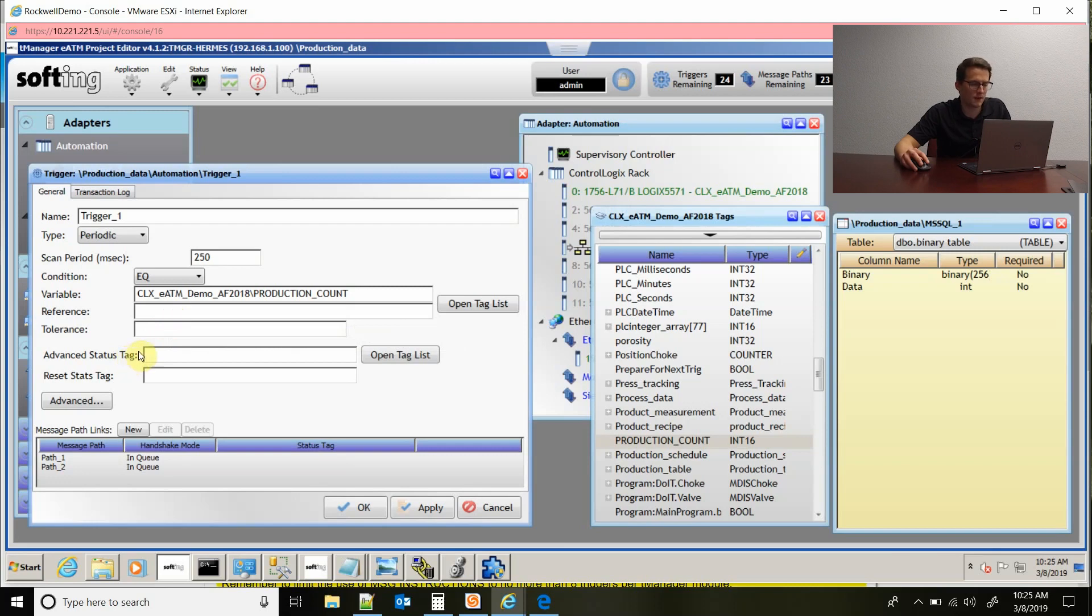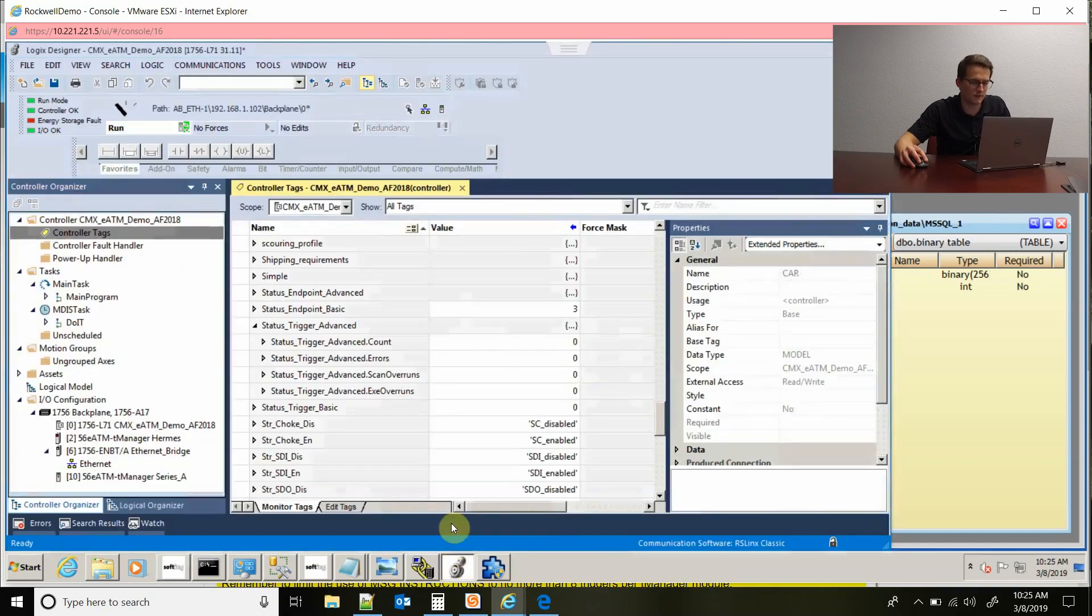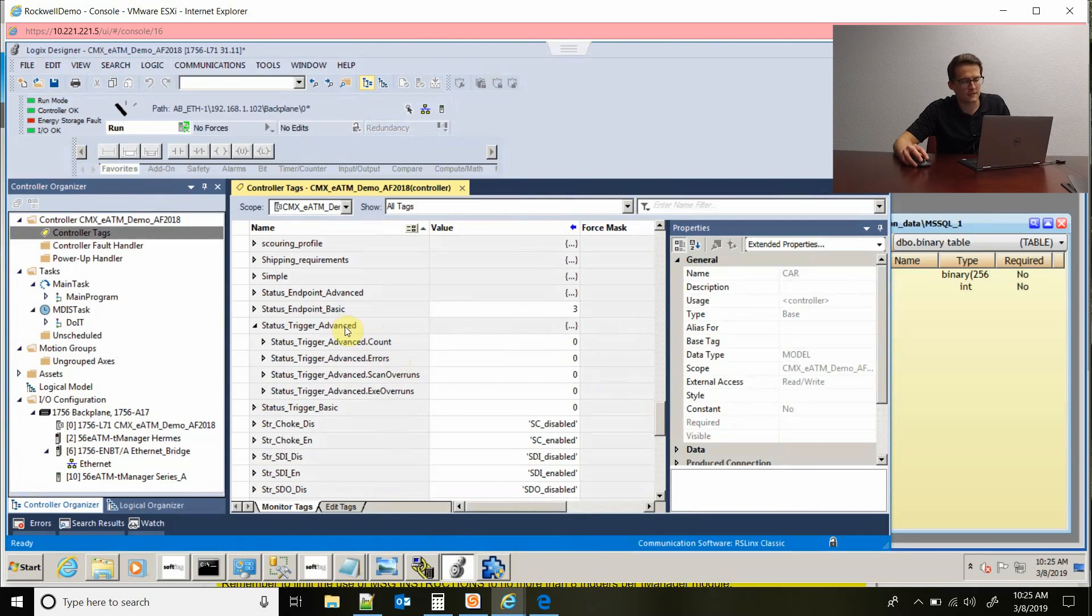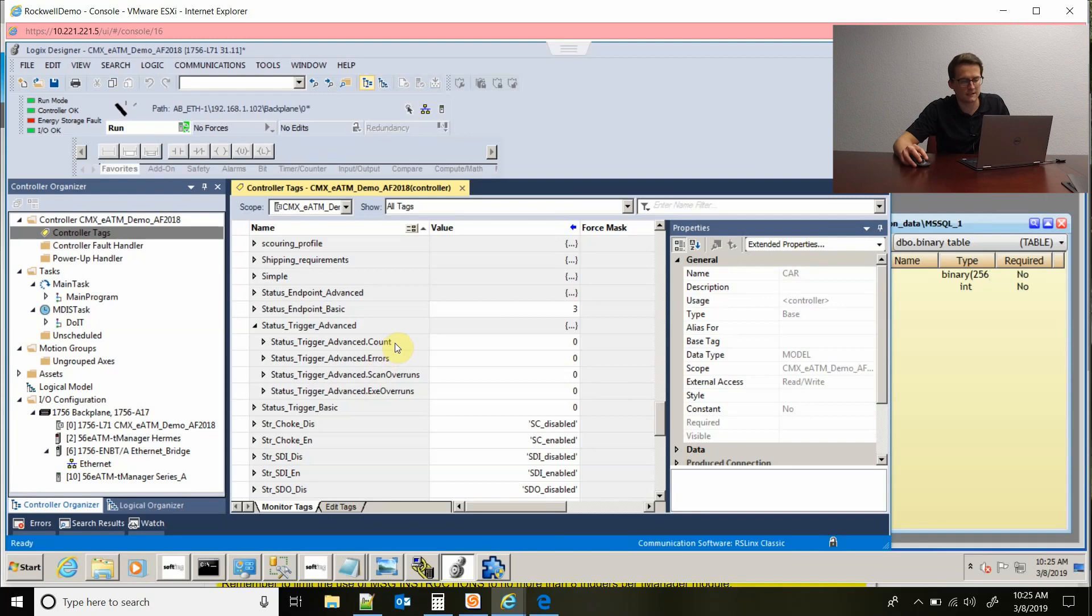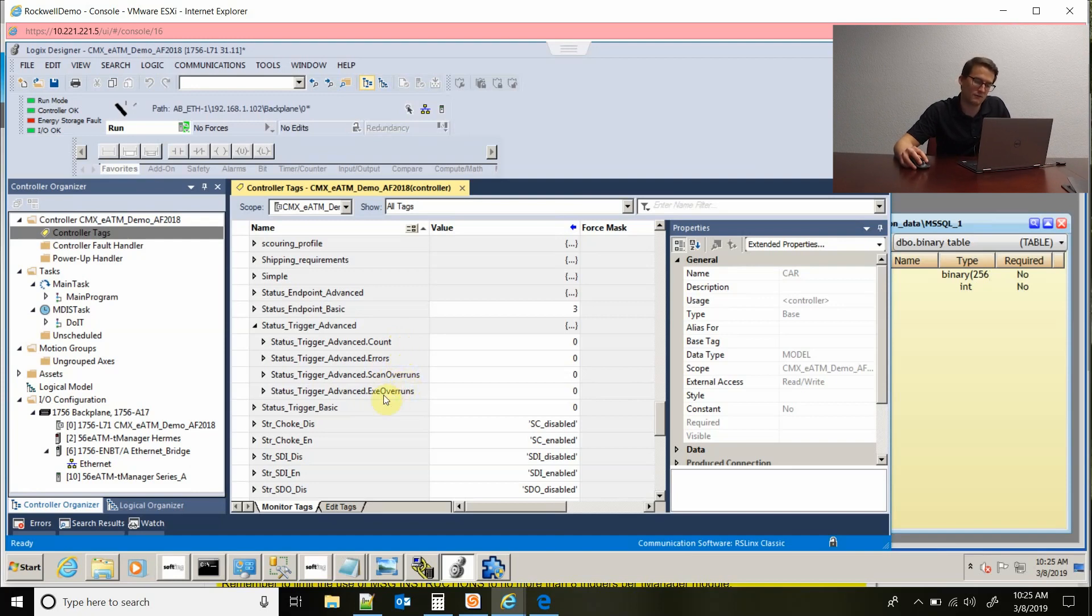There's also an advanced status tag that you could set up in Studio 5000. So you would configure this in Studio 5000. I have one set up and the status tag looks like this. You would need to have these values in here. What that is is it tells you a count of how many transactions have fired, if you've had any errors, if you've had any scan timeouts, scan timeout overruns, or execution overruns.